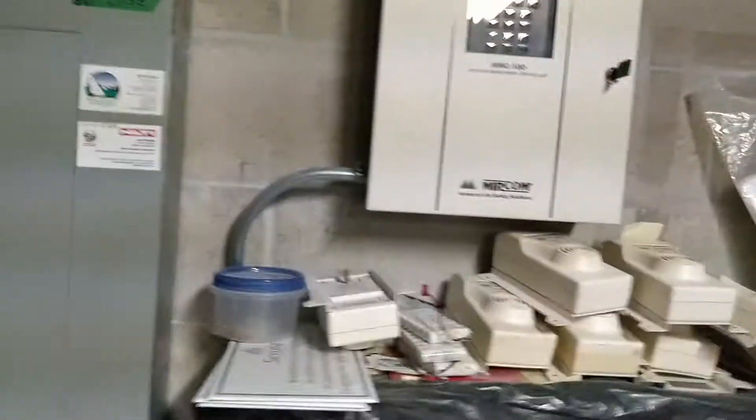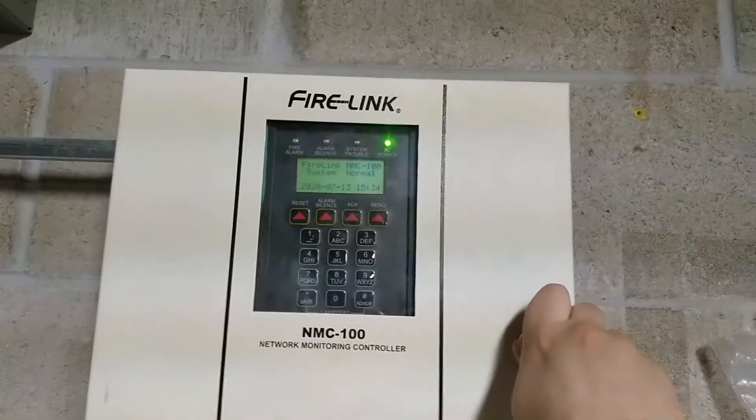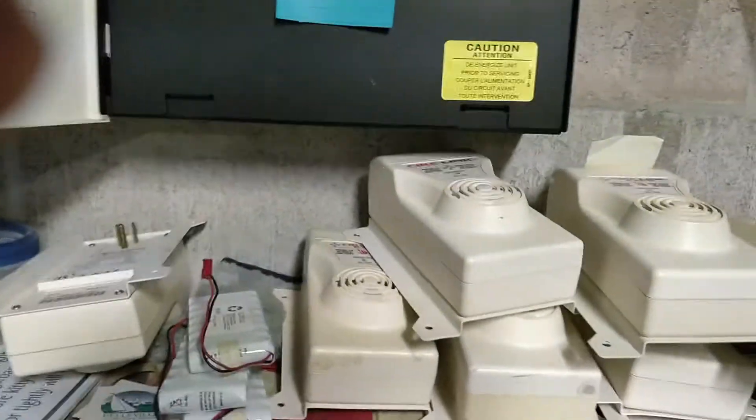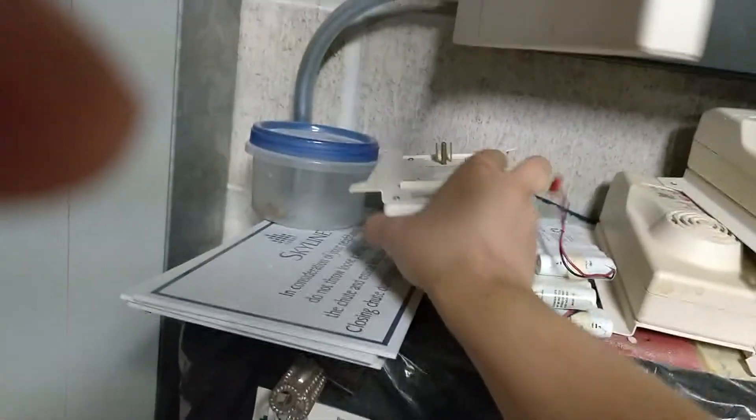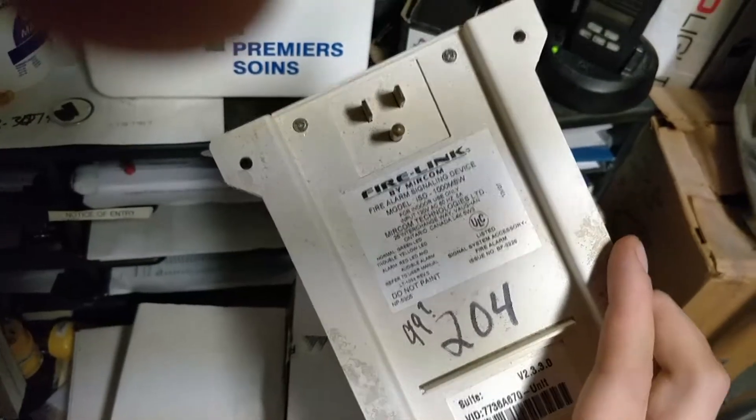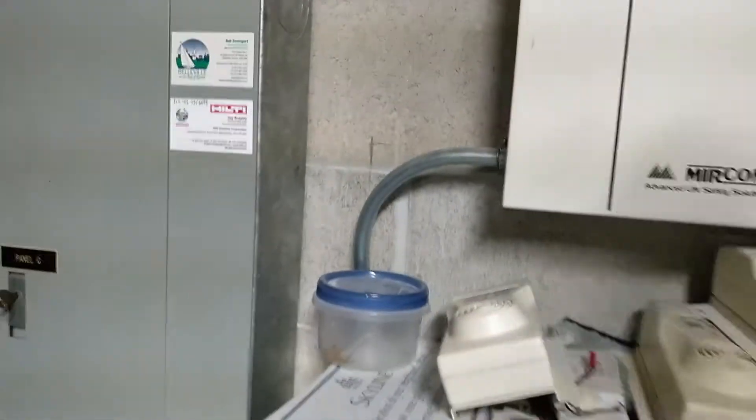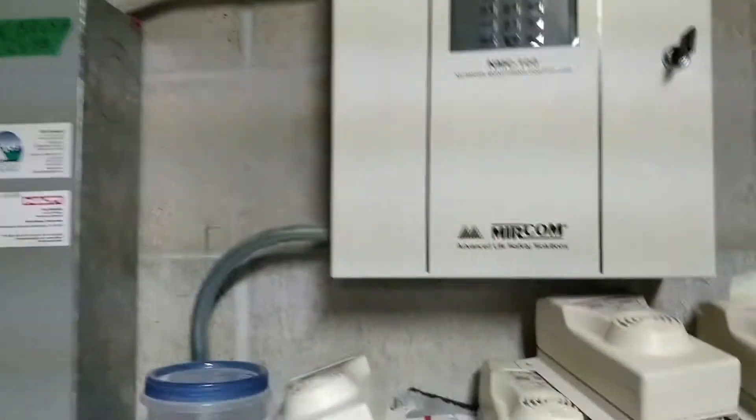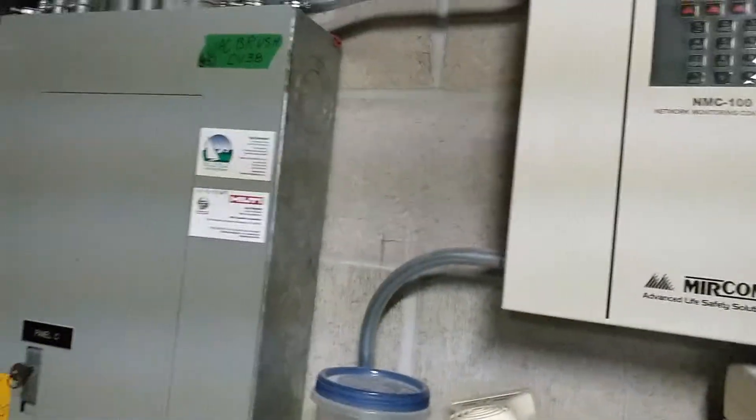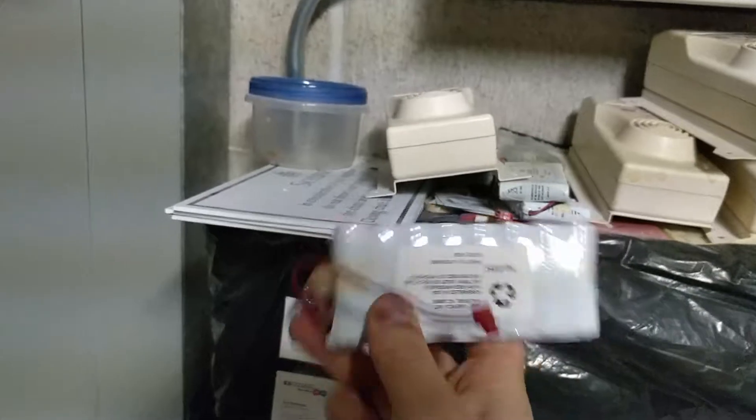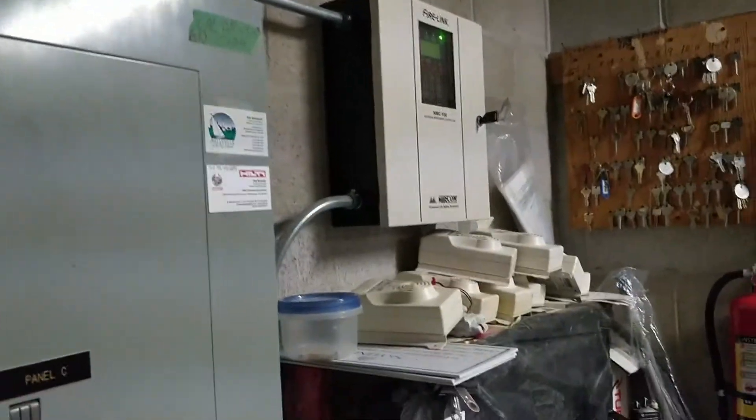This place also has this junk here, this Fire Link thing. I don't know if you guys are familiar with these, but they're basically garbage. They're in-suite horns. You plug them into an outlet and it actually sends its tone through the AC wiring of the building. But you can imagine it's just a nightmare for service calls, people unplugging them. These are the batteries in them, they're a pain in the ass to get. This building is actually one of three buildings on this site, and this is the last one left with that system in it. We've ripped them out all the other buildings. So basically I'm just going to leave that thing running because I don't want to shut it down and boot it back up. Last thing I need is more problems today.